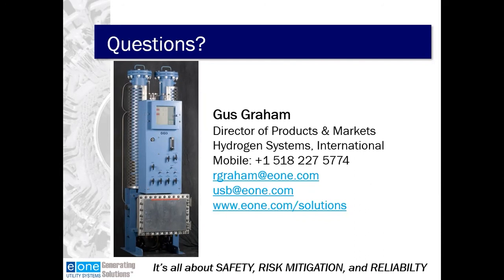Okay, another question. What parameters dictate the size and/or type of dryer? So the eone dryer is one size fits all. The amount of desiccant we have and the flow rate we obtain with the circulator, we can dry and maintain dew points on generators as large as 1,200 megawatts effectively. Again, it comes down to how big of a leak of water into the generator that we're looking to remove.